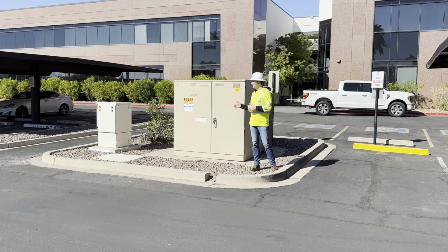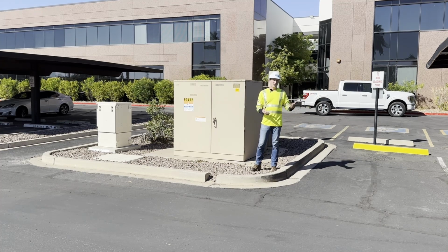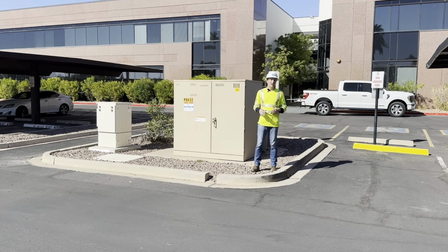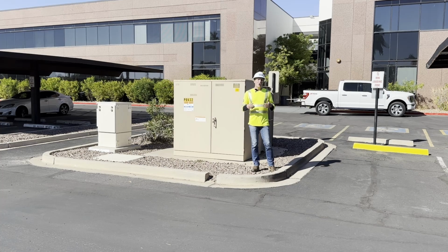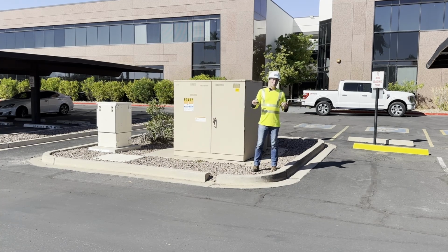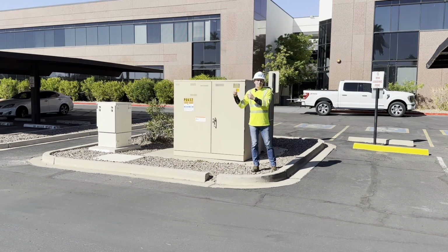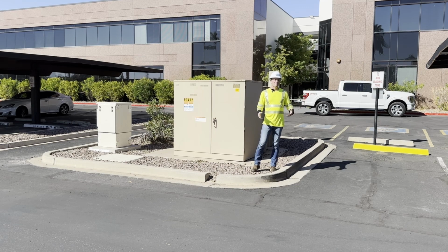The utility can also give you that fault current information, but it's always important to know the transformer's impedance so you can anticipate and calculate the worst case scenario. We'll do a whole video about the difference between asking the utility for that current versus doing an infinite bus calculation to model your system off the worst case.